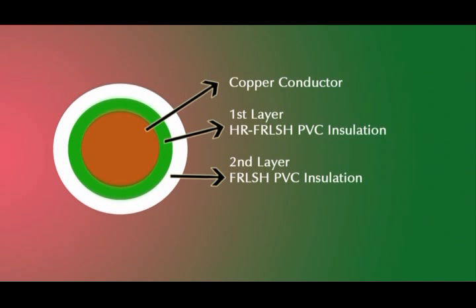FRLSH insulation. The second layer is a thicker cover for the HR FRLSH insulation. It restricts the spread of flames. In effect, it almost wipes out any possibility of smoke, toxic and corrosive fumes. There is virtually no possibility of the occurrence of any such hazards.